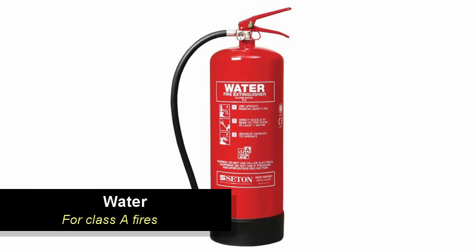They allow the user to direct water onto a fire from a considerable distance. A 9-litre water extinguisher can be quite heavy, and some water extinguishers with additives can achieve the same rating, although they are smaller and therefore considerably lighter. This type of extinguisher is not suitable for use on live electrical equipment.